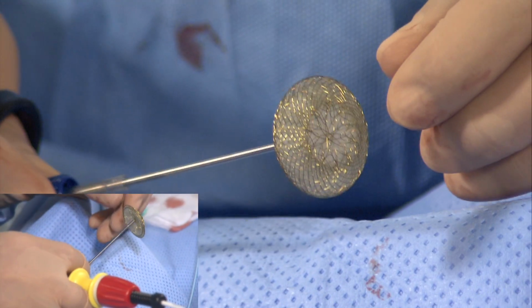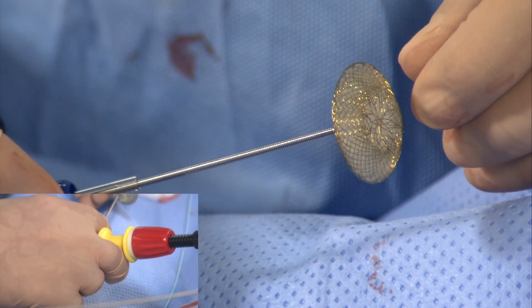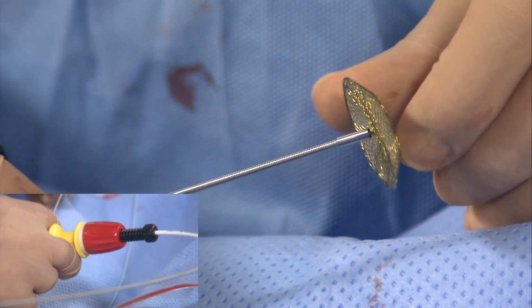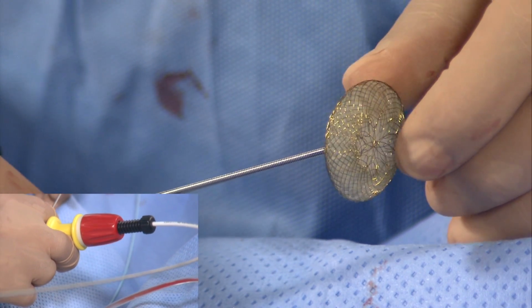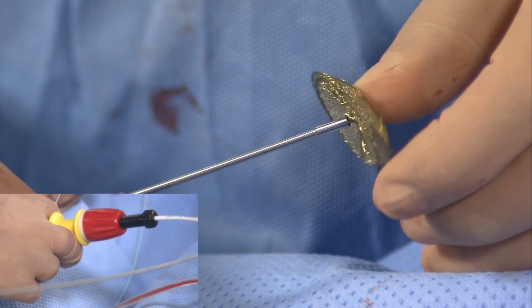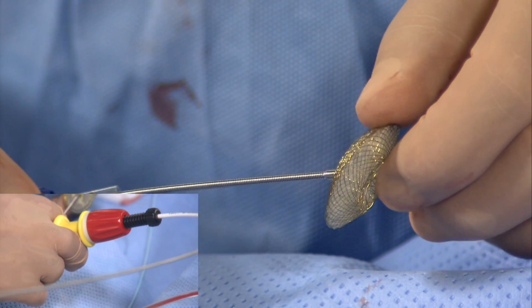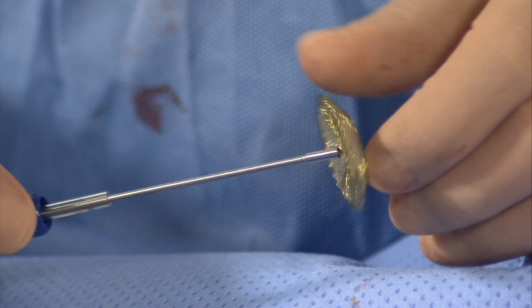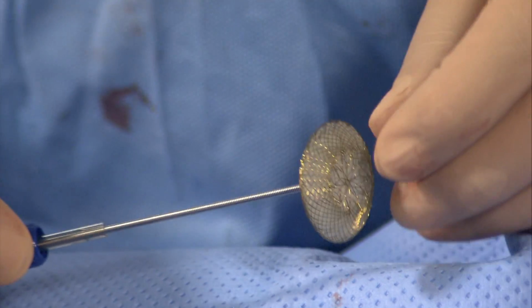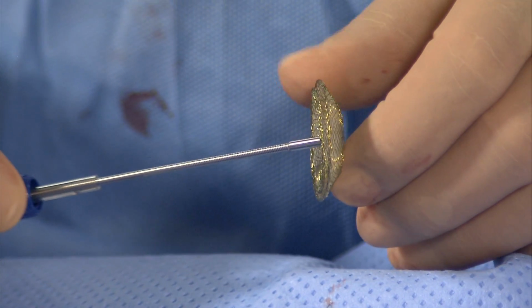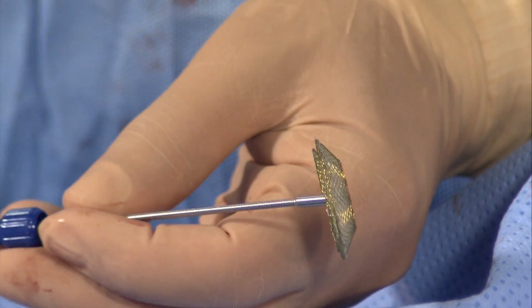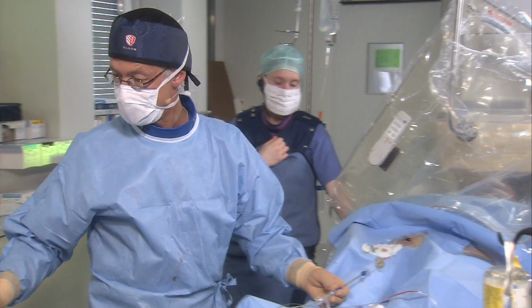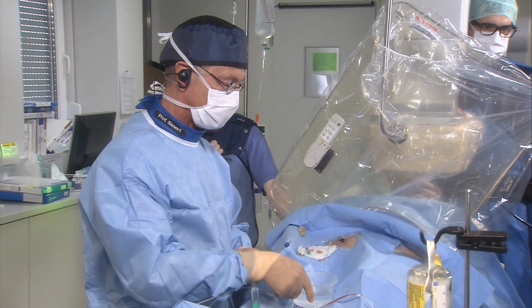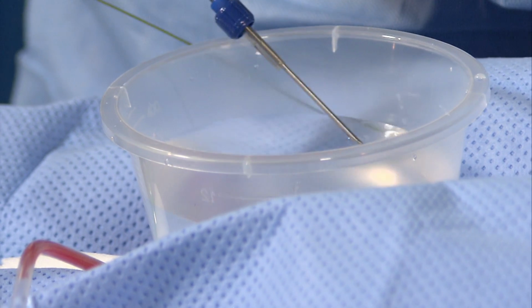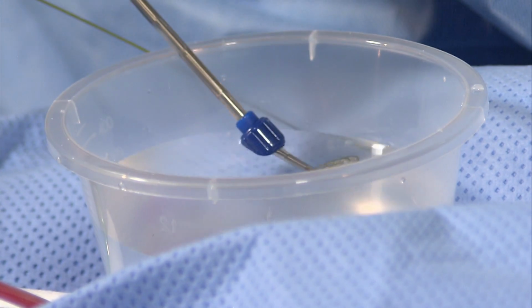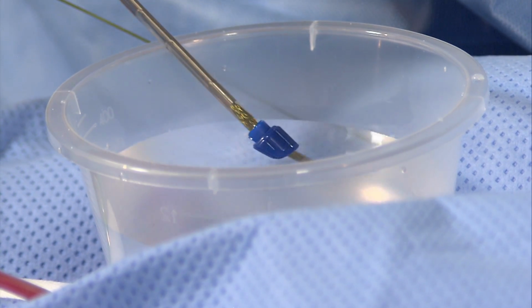And the advantage of that technique compared to a screw is that the connection is flexible. You can see here it's a very flexible connection, which means you can see the device before it is released in a more relaxed status than what is the case with older devices like the Amplatzer. Also, it was the case with the old Occlutech device. So these are the advantages of this particular device. So now let's pull it back into the loading tool. And you can do this underwater, as I'm currently doing here. You can also just pull it in and then flush from the back end of the flushing tool.